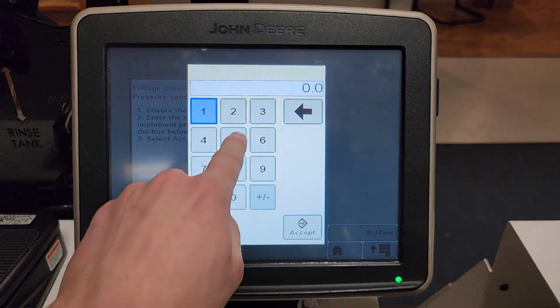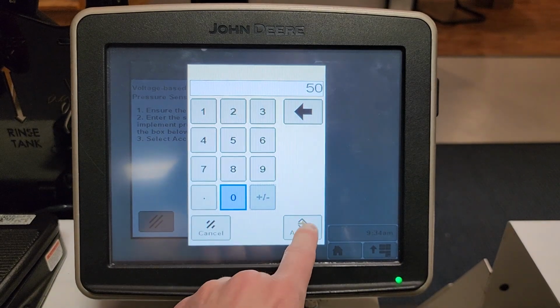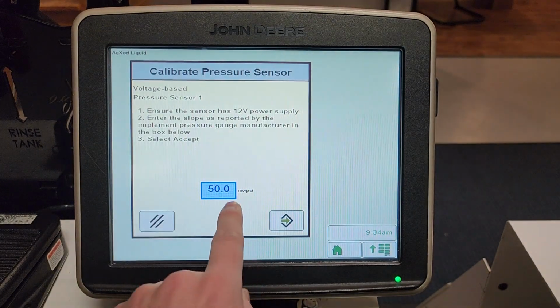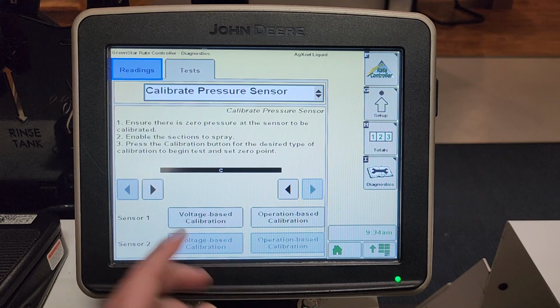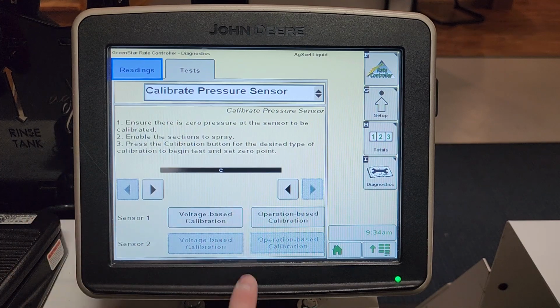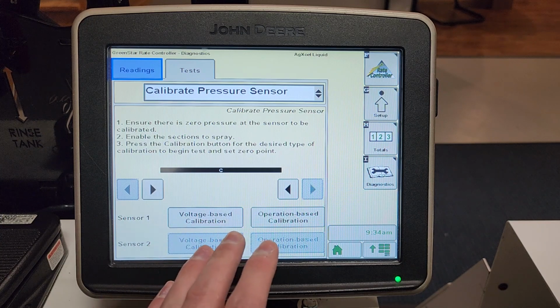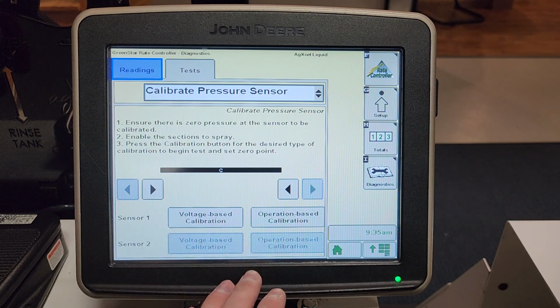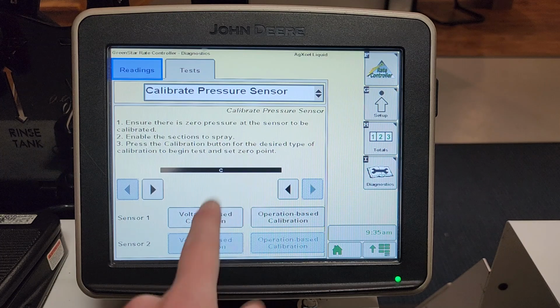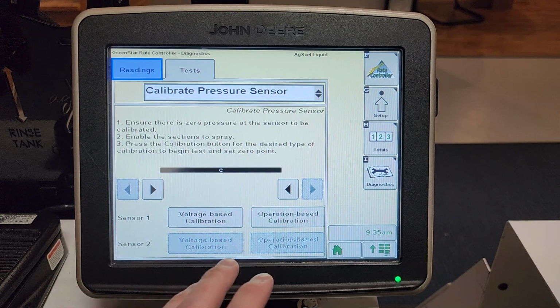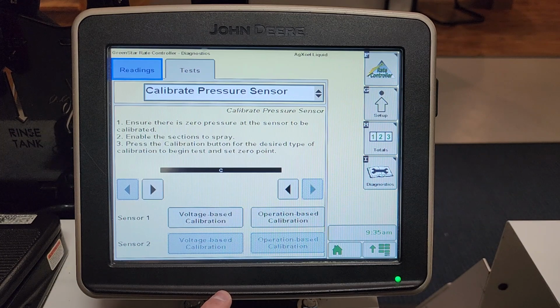We will do a voltage-based calibration, and you would do this at 50. And this would be your setup. Once you're done, then that would be your setup process. Typically what I like to do is, when you set this up, make sure you have 0 pressure in your pump system. But I like to unplug the pressure transducer, set this up, then plug it back in, and then we know for sure that the pressure transducer would read 0 when you set it up.